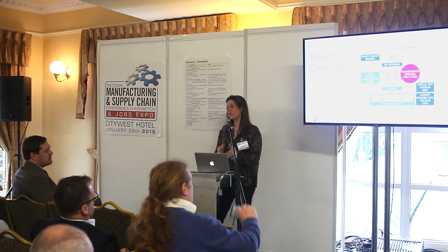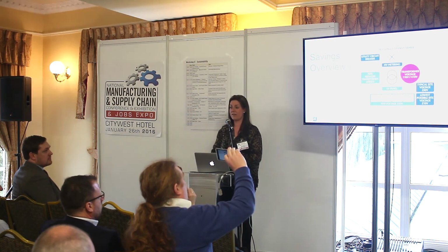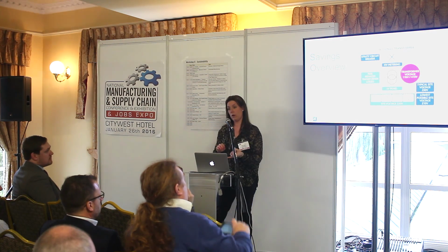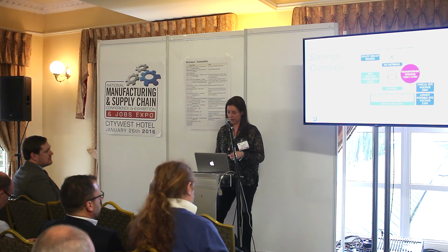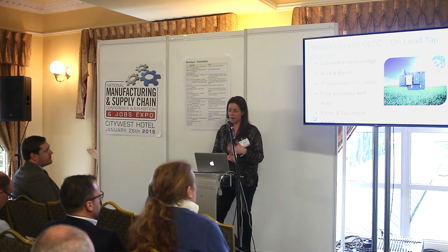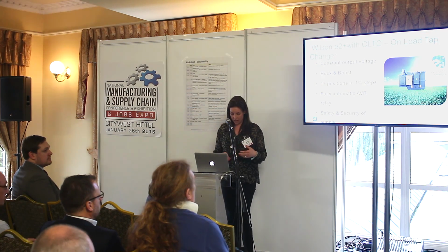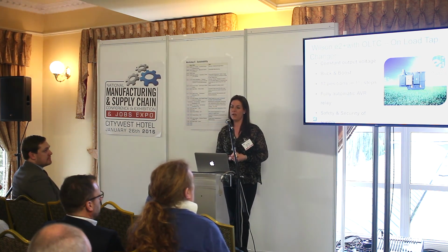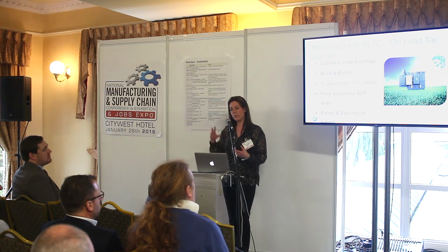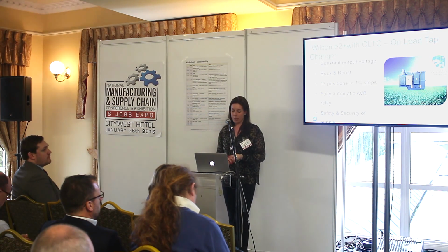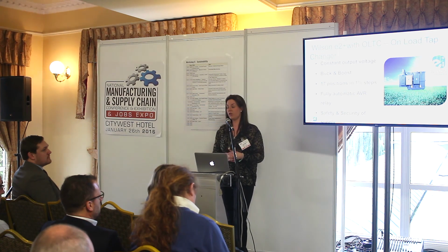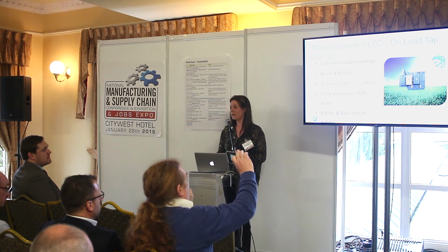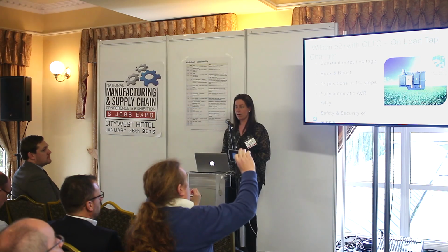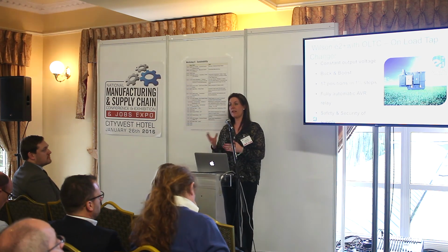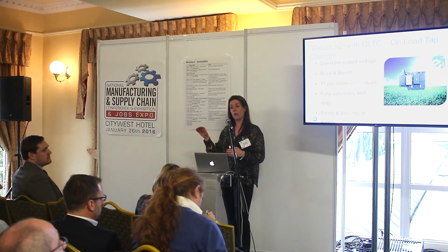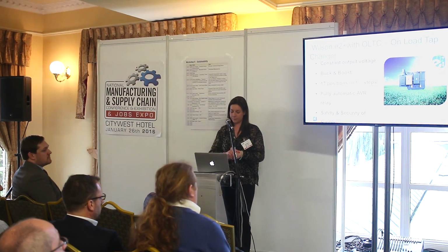And in a case study later you'll see where one of our customers has benefited from both losses and voltage optimisation. Another thing that's come into play is this dynamic voltage optimisation, where your voltage is going up and down quite a lot. We do an on-load tap changer version of the product, so it has a 17-position AVR relay. So you can adjust - you set your voltage at commissioning and then it will keep that voltage and maintain it throughout.